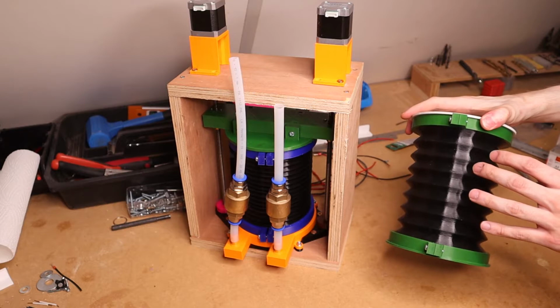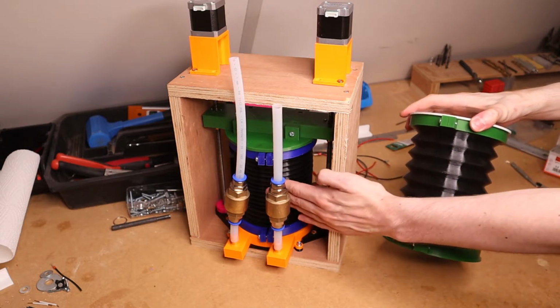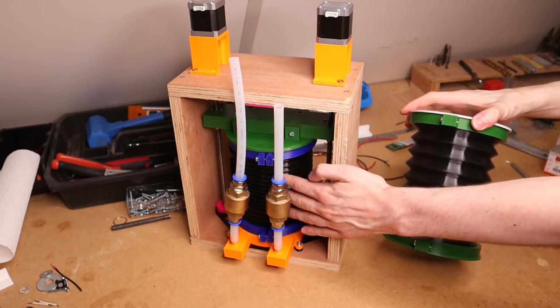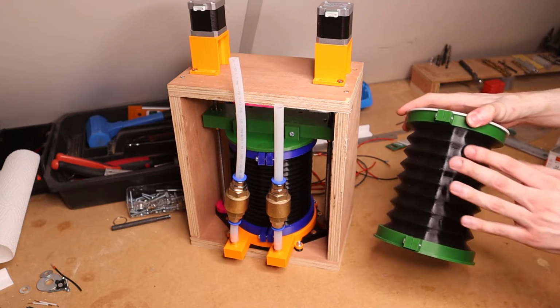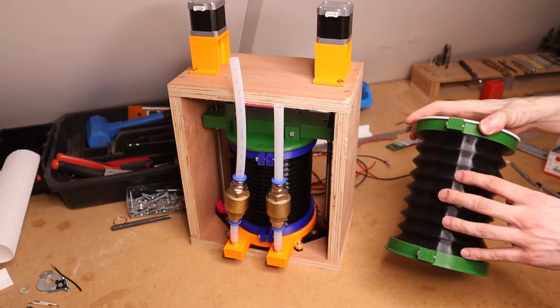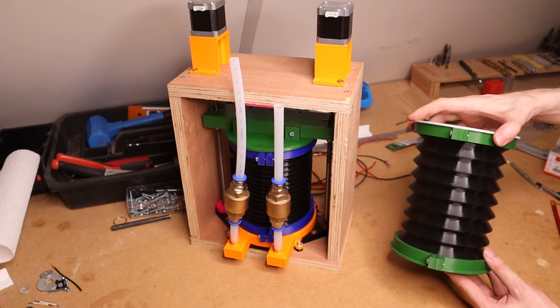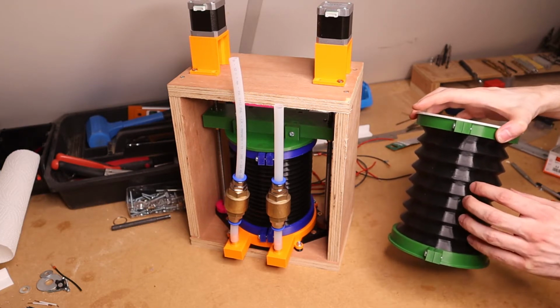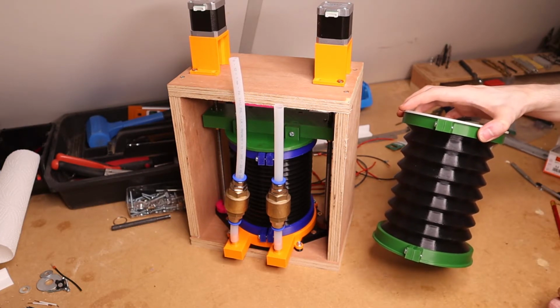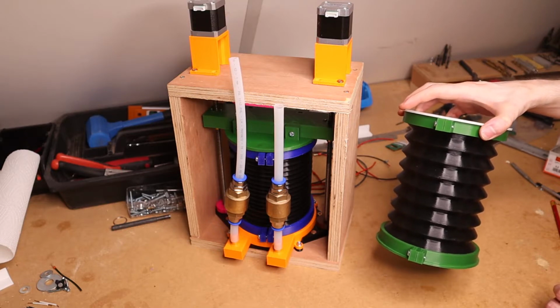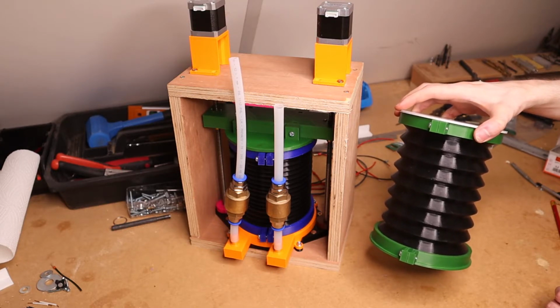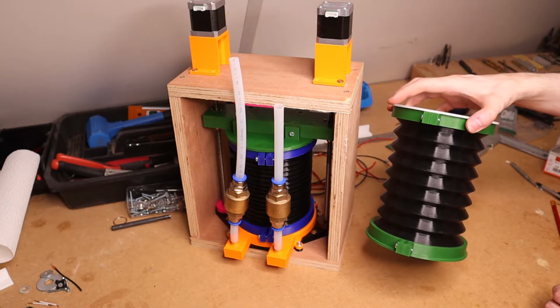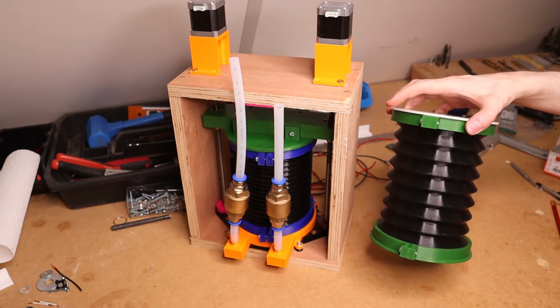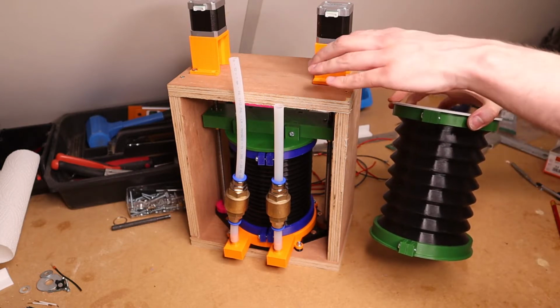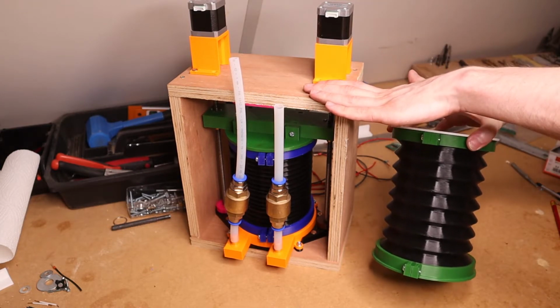And so the difference between this bellows over here and this one here is that this one has a wall thickness of 0.9 millimeters, and this one is doubled up. This has 1.8 millimeters thickness on the walls. So I'm expecting this to be a little bit more durable. I'm also expecting to receive a medical grade bellows, a commercial one. So that of course would be a lot better. It does have a little different dimensions though, so I should probably change out the pump module as well at that time.